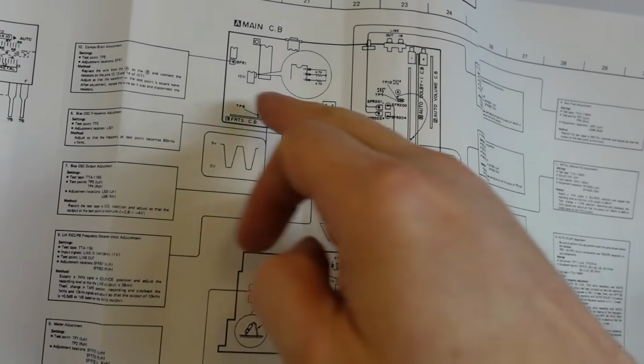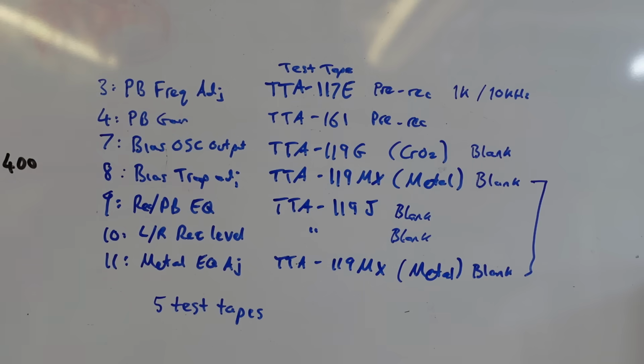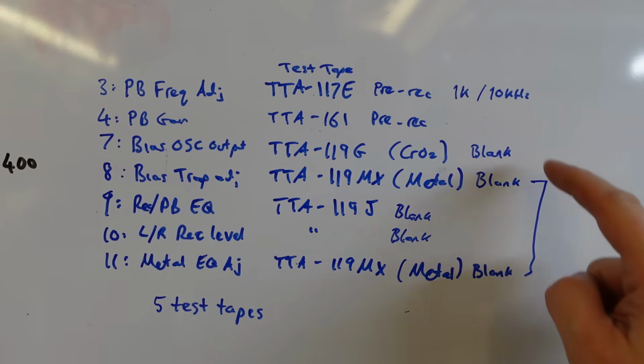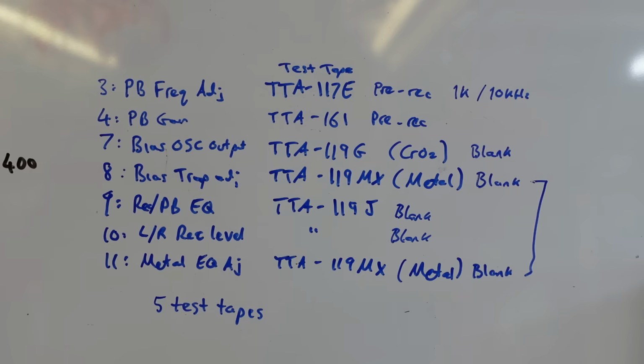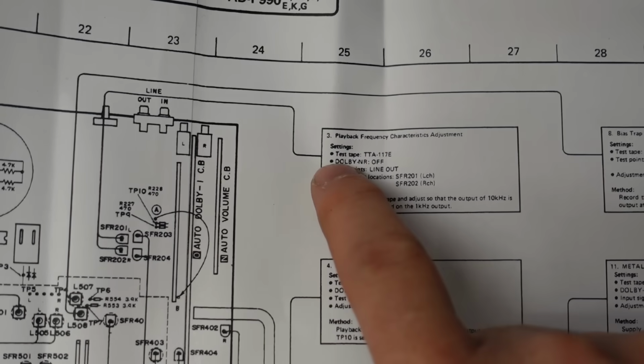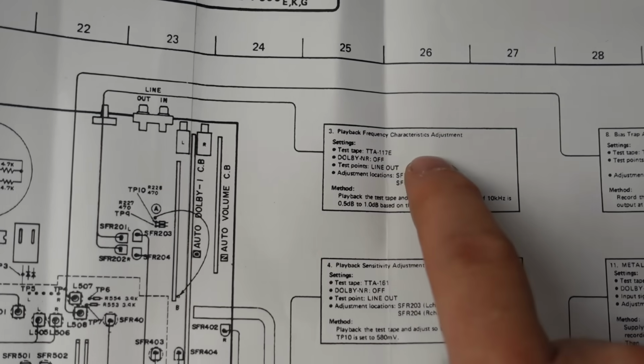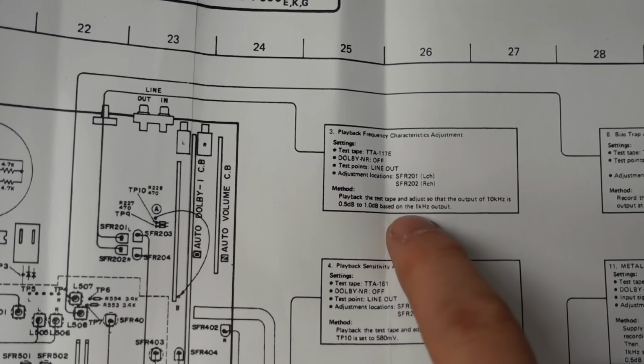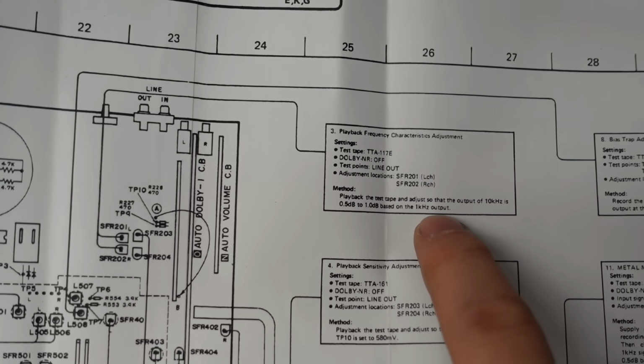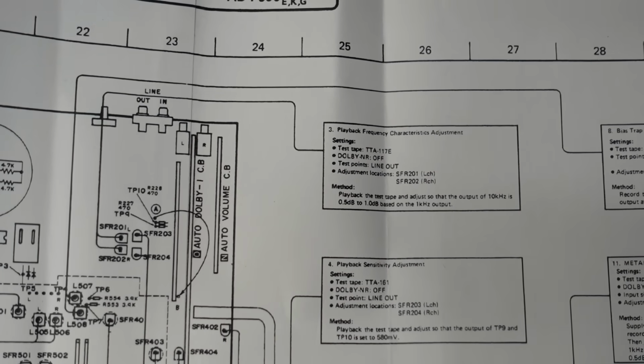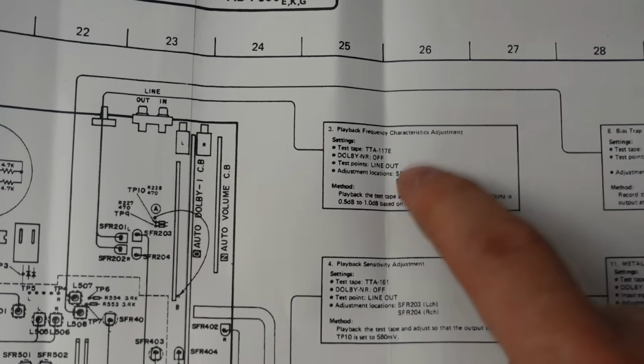And this is the calibration procedure for all this, and it refers to lots and lots of different test tapes you need. I've actually listed them out. It turns out there's only 5 different ones. Unfortunately, 3 of them are blank. The first step of electronic calibration, part 3 here, is to adjust the frequency adjustment. That requires a test tape with a 10 kHz and 1 kHz signal on there. It's pre-recorded and I haven't got one. I'll have to skip this step.